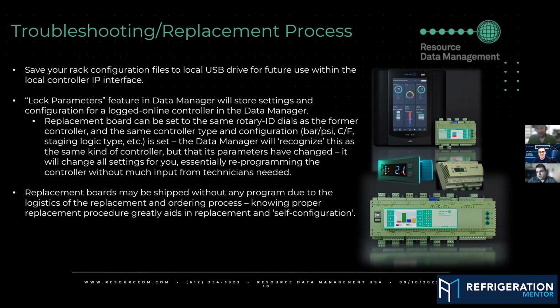If you do run into a situation where you're replacing a rack controller or a case controller, the best thing to do is to make sure that controller is set for the same control type. So if it's a rack controller, make sure it's set for fuzzy logic. Make sure it's set for 2 suction groups and a gas cooler receiver control group. If it's a case controller, make sure it's set for a case and not a cold room. And then set the rotary IDs to identify the controller to the data manager. Then plug your CAT cable in.